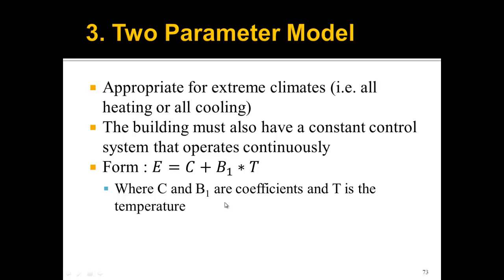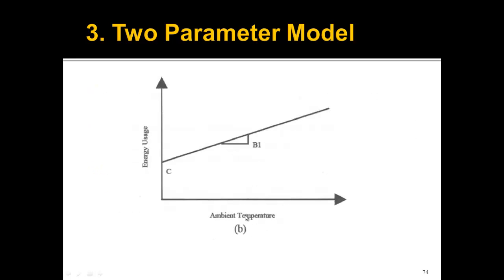The form here is that the energy use over a certain time period equals some constant C plus some constant B₁ times the temperature. An example of how to get these two constants is just like when we saw linear modeling. We would put our energies, our energy use, and our temperatures in Excel, and we'd get the two constants from that best fit line. How this looks in graphical format is that, in this case, as the ambient temperature goes up, the energy usage goes up. And how much it goes up is the slope, B₁. And if the ambient temperature is really cold, the intercept here is C. That's the basic idea of a two-parameter model.